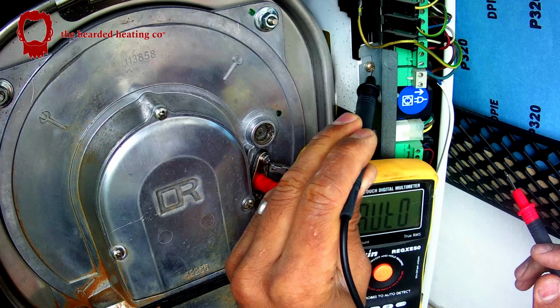So if that is good, I'm going to put it back together, power it back up again, and check for polarity - make sure polarity and earth is good, because it could be that the earth to the property has just dropped, or to this one electrical circuit. It happens - I've been to way too many jobs where the boiler works perfectly well, and then all of a sudden the earth just drops off due to a poor connection.